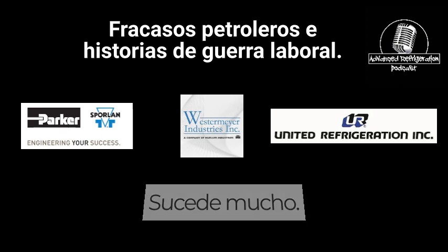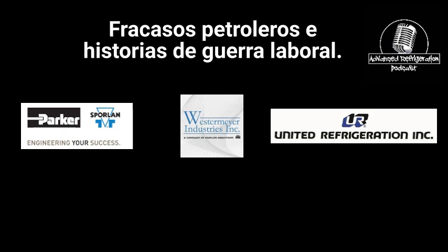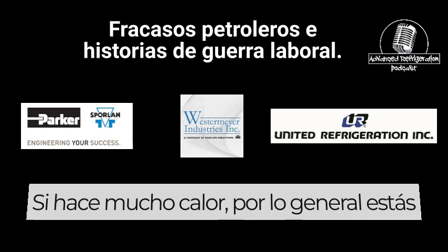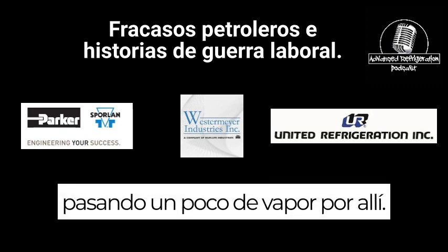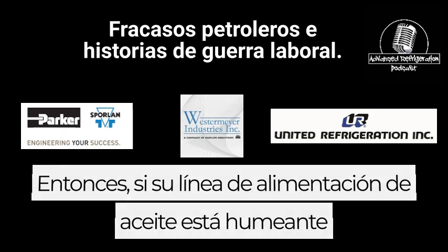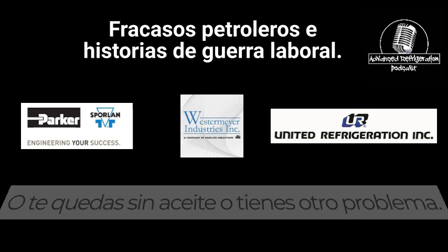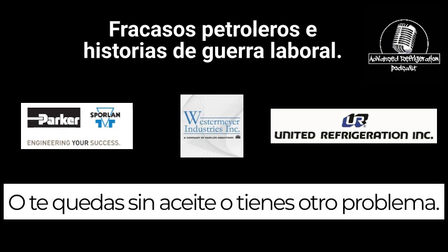Yes, correct. I mean, it happens a lot. One thing to look at, just check the oil feed line. If it's smoking hot, generally you're getting some vapor through there. So if your oil feed line is just smoking hot going into that oil float, you're getting vapor in there. You're either out of oil or you have another issue.